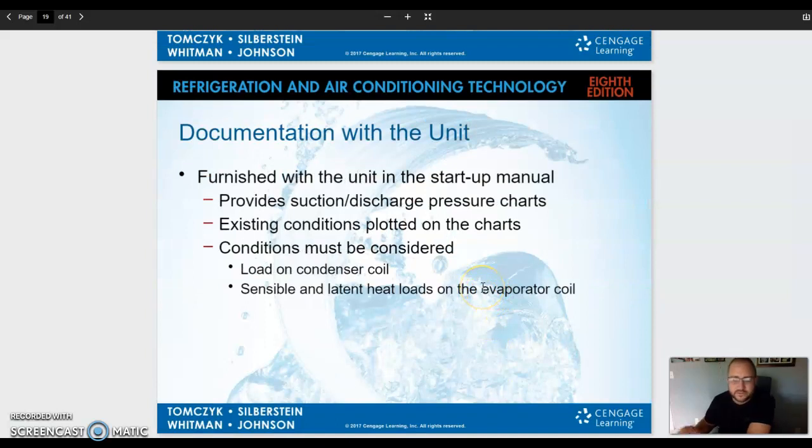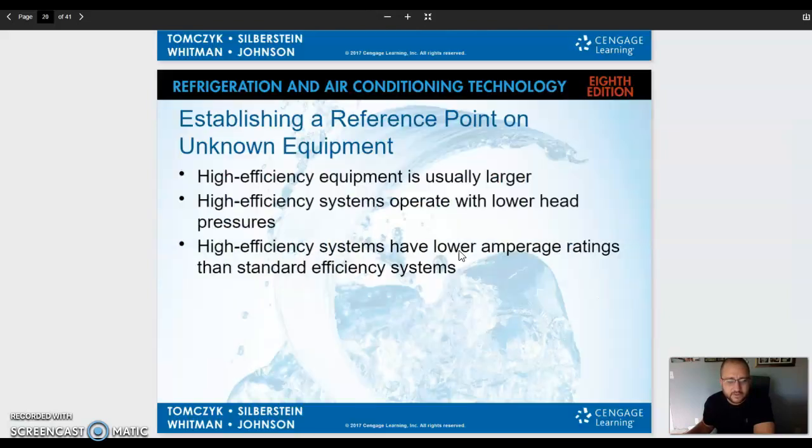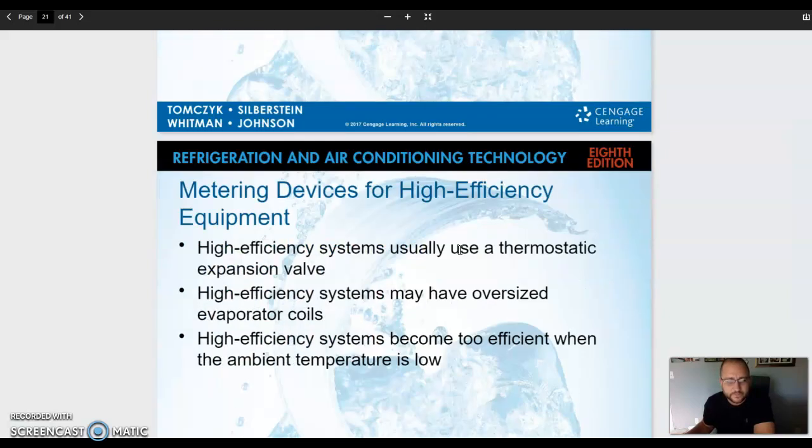Another thing, the superheat rating, if you have a TXV, you're going to look at superheat, but you're going to go by subcooling, because the job of the TXV is to maintain a constant superheat. So all the information is going to come into play. Delta, your vapor saturation, your liquid saturation, temperature differences between indoor and outdoor. So you're factoring everything in. So there's no just take a reading and you're good. You're going to factor it all in to make sure that everything's running as it should.